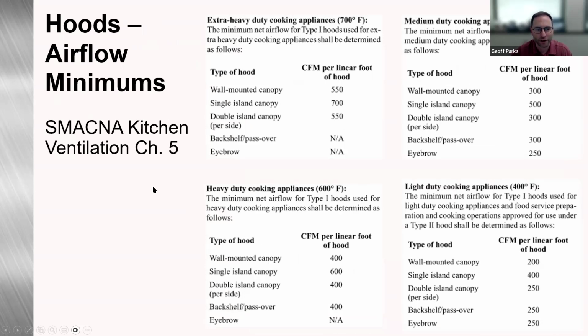Here we have out of Chapter 5 of the SMACNA kitchen ventilation. So this is just the minimum airflows for the different types of hoods: extra heavy duty, heavy duty, medium duty, and light duty. Also, we've added some temperature ranges. So 700 degrees Fahrenheit for our extra heavy duty, 600 for heavy duty, 400 for medium duty, and then 400 for light duty appliances.